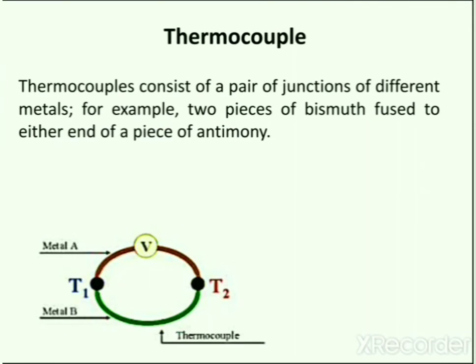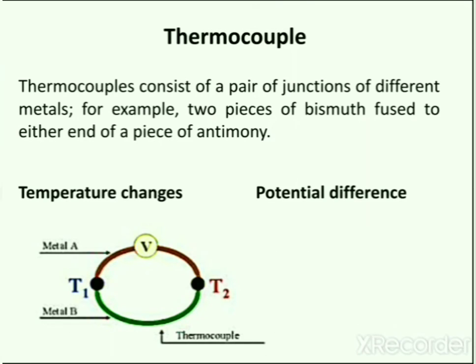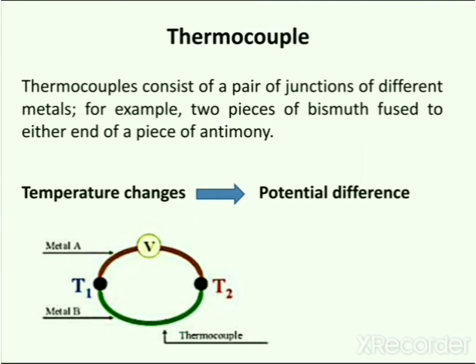The thermocouple detector consists of a pair of junctions of different metals — for example, two pieces of bismuth fused to either end of a piece of antimony. The sensing element is composed of small thermocouples on a silicon chip which absorb the energy and produce an output signal. This detector works on the phenomenon that when a closed circuit is formed by joining two dissimilar metals at two junctions maintained at different temperatures, an electromotive force is induced in the closed circuit.